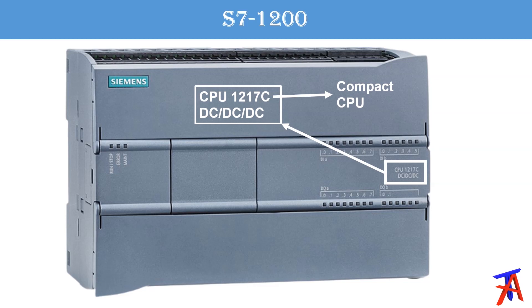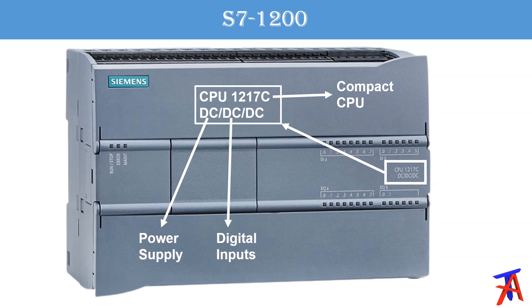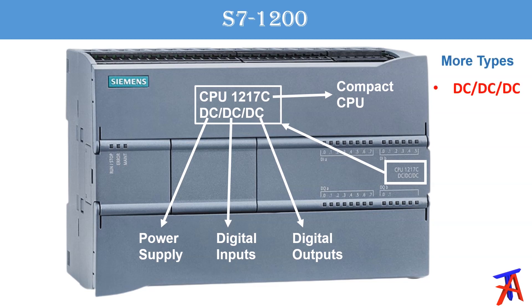The 'C' denotes compact CPUs, meaning it has onboard digital inputs and digital outputs. There are three 'DC' designations on the PLC: the first DC means the power supply is 24V DC, the second DC means the digital inputs are 24V DC, and the third DC means the digital outputs are transistor-type DC outputs. Different variants available are DC/DC/DC, DC/DC/relay, and others.